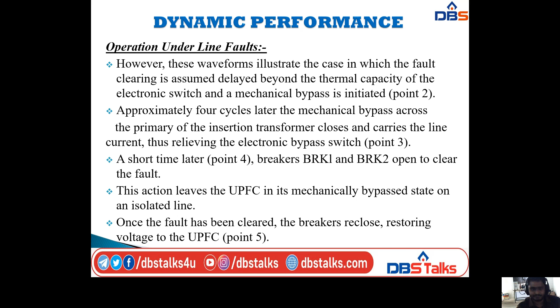During the reinsertion procedure, the series converter forces current, that is I_SCR, through the series transformer to match the line current, I line, driving the current through the mechanical bypass to 0 in order to achieve a transient-free reinsertion. At this point, the value of the series injected voltage is fixed and a signal is sent to open the mechanical bypass, that is at point 7.